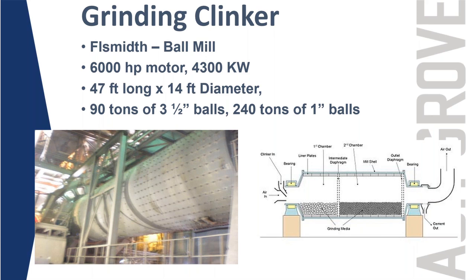A few years ago, we had it go to ground, and the winding in there melted together, and we had to take that to the nearest place we could get it rewound and then dipped in a dip tank, which was in Louisiana. So that gives you an idea of the size of things that we have out there at the plant. It's sometimes hard to get the maintenance done locally. It's a very big operation.